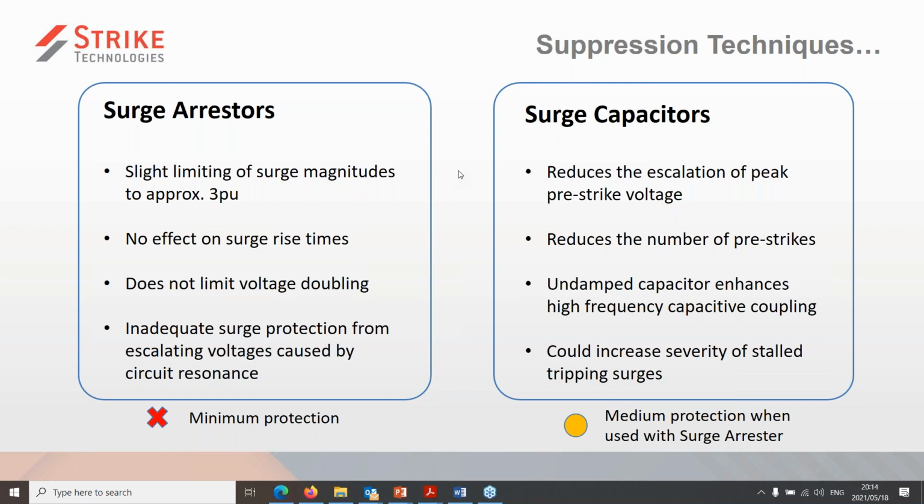Conventional surge arrestors don't really provide adequate protection, as the clamping voltage is pretty much higher than the motor impulse insulation withstand levels. And opposite to that, lower clamping with a surge arrestor might inevitably cause thermal runaway due to leakage currents at fundamental frequency conditions.